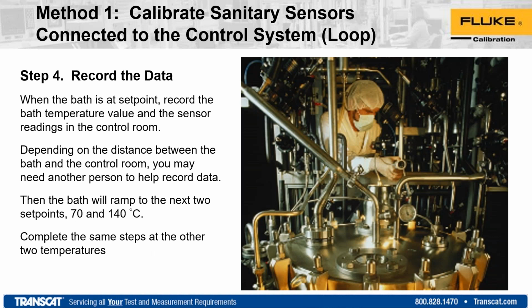So now that we're starting to record the data, you're just going to have to do this manually. We've semi-automated it, but for the actual data collection, since we've left that sensor in place, the only place we can really see what it's reading now is back at the control point. So we'll assume that the unit has now come to 0. It's stabilized. We look at our bath setting. It says I'm at 0. We know that the uncertainty for it is plus or minus 0.1. And then we can walk back to that control room and see if we're within the spec that we need to be.